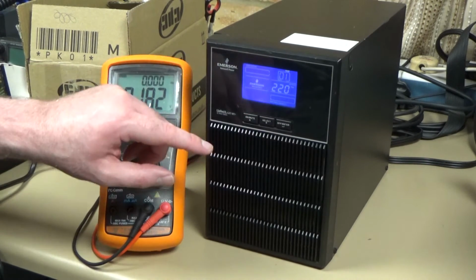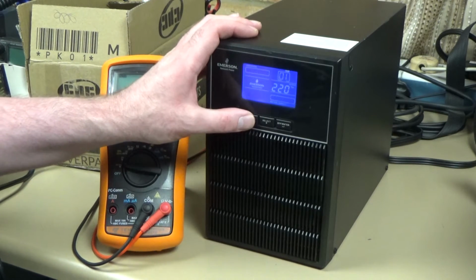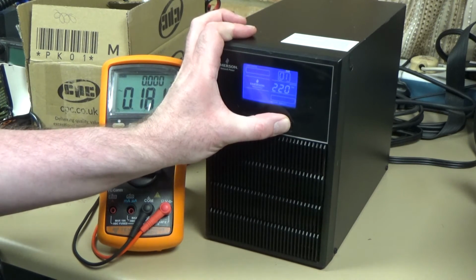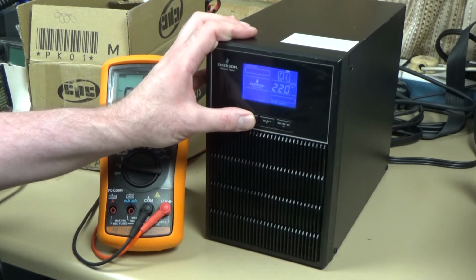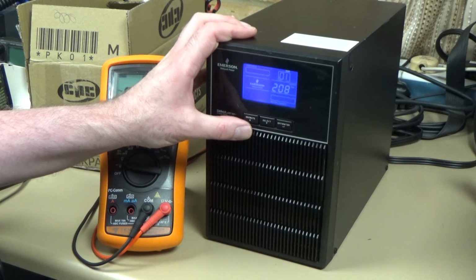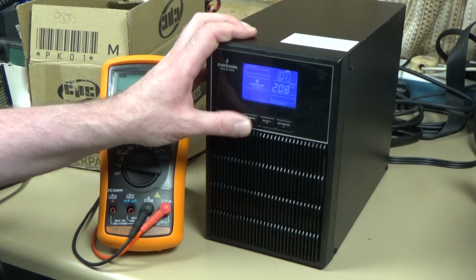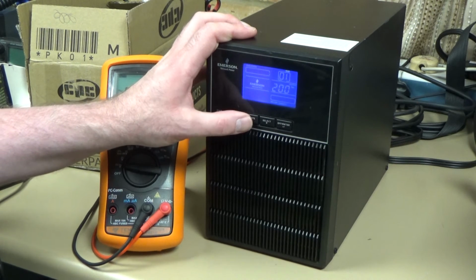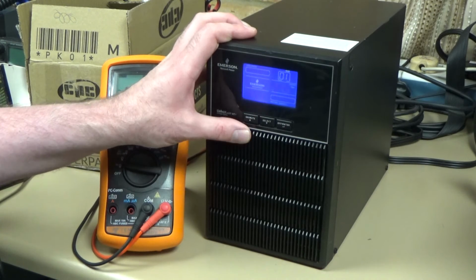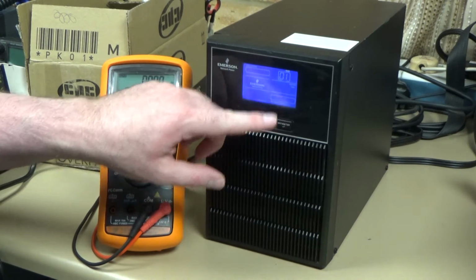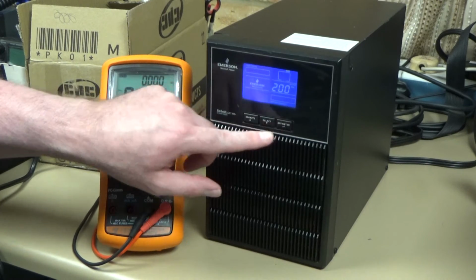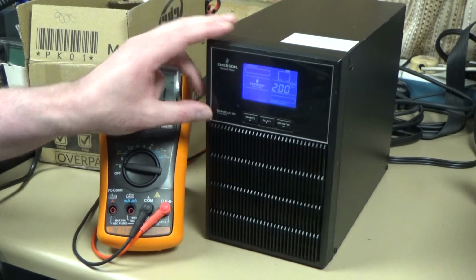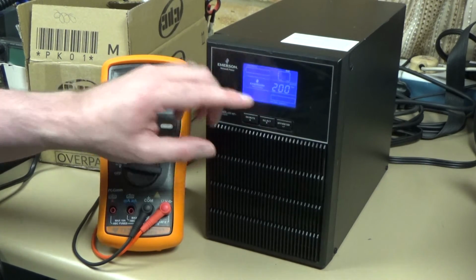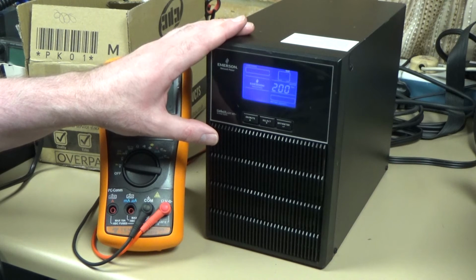Currently it's set to 220, interestingly. So if I select that first, I can take that down to 208. I can take that down again to 200. Unfortunately, I can't go below 200, it goes back up to 240. So the lowest I can set is 200, which is interesting because if you read the user manual for this device, it says the lowest you can go is 208, but this one goes to 200.